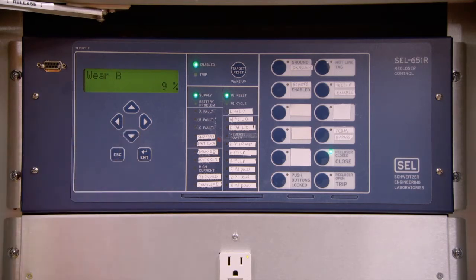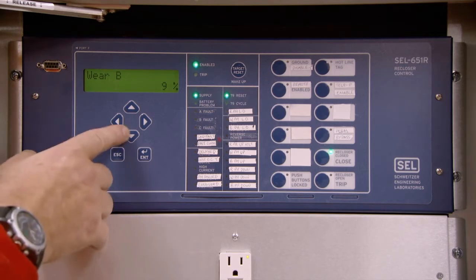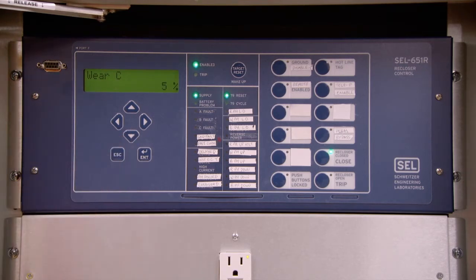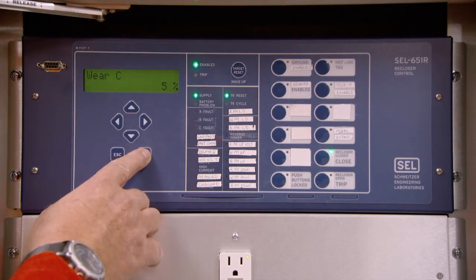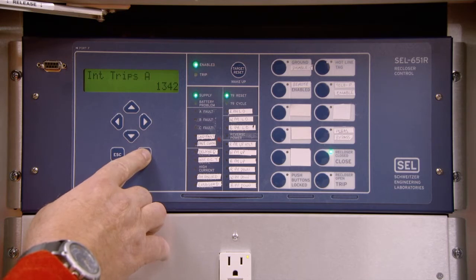This will return one to the wear monitor A. Pressing the down arrow will scroll through wear monitors B and C. As seen here, most of our faults have been applied to one phase for our testing purposes. Other phases were tested for functionality and balance verification. Press Enter to escape and return to the main scrolling screen.